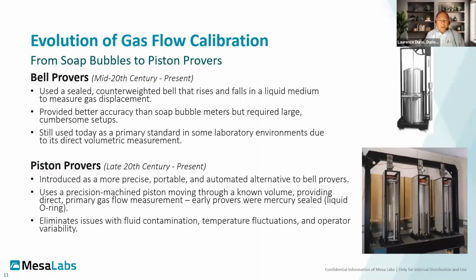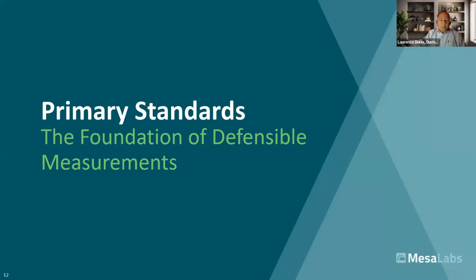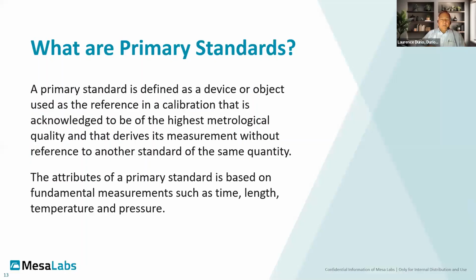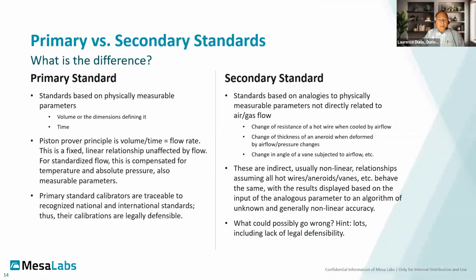and were not very field portable. Piston provers came in, basically more precise, more portable, as you can see on the extreme right side. Perhaps not as portable and field friendly as we'd like, but basically they measured the movement of a piston up a cylinder, timed automatically. We try and use primary standards to the greatest degree possible. They're traceable, they're defensible. A primary standard is a device or an object that is used as a reference that is derived from physical standards, measurable: time, distance, pressure, temperature, fundamental measurements that are traceable to national and international standards.